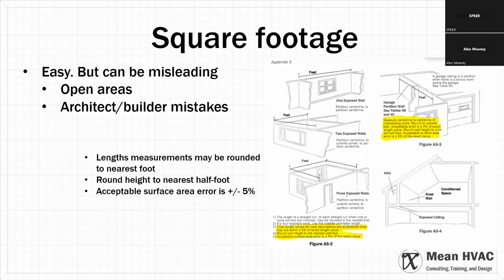There can be some snags when checking square footage. First of all, square footage technically isn't very important at all. Heat only transfers through the square footage at the lowest floor, at the bottom floor and above the garage in Texas. And if you're on a slab and we're talking cooling load, it doesn't even do that. There's literally no heat transfer there. If there's any heat transfer, it's going the right direction, so it's a net cooling effect. There is no cooling load on the floor.